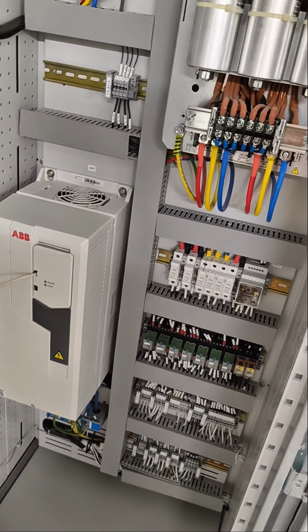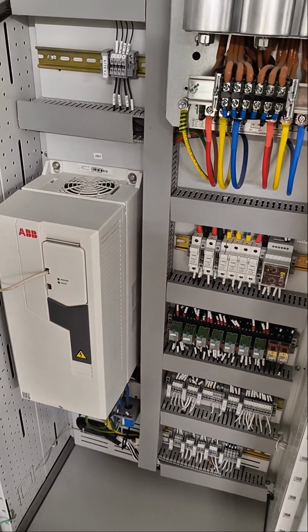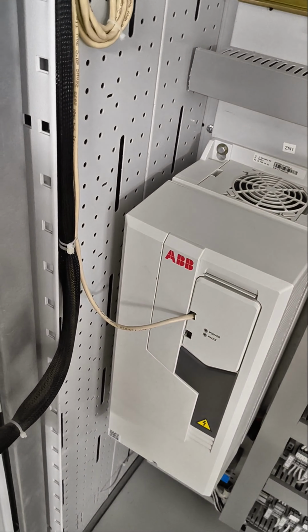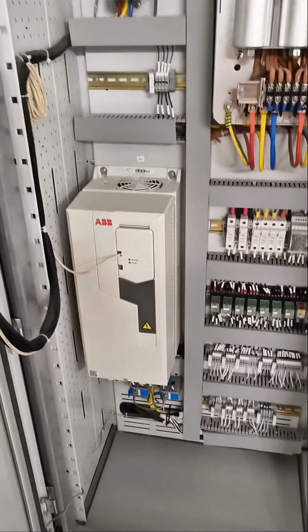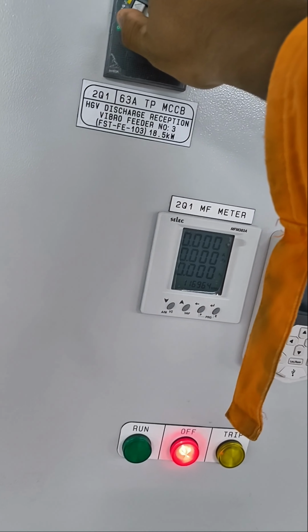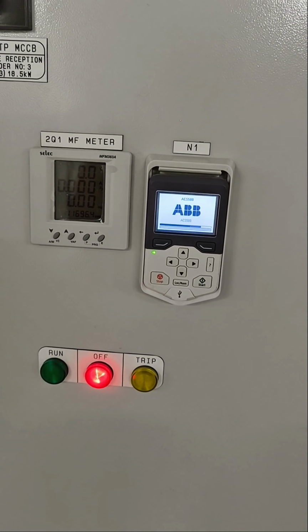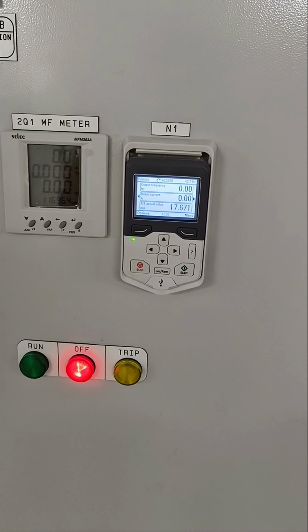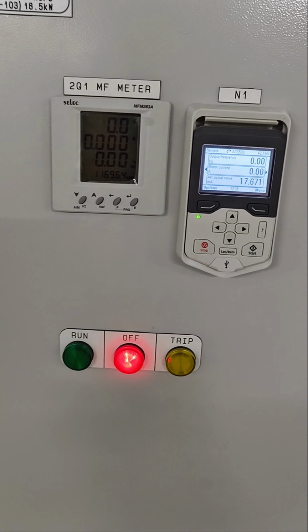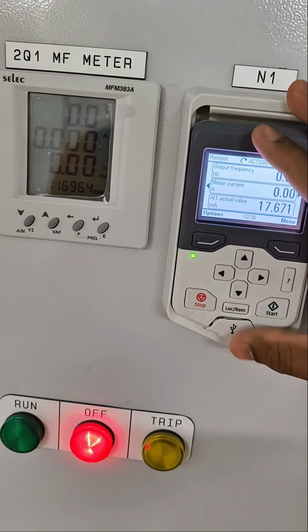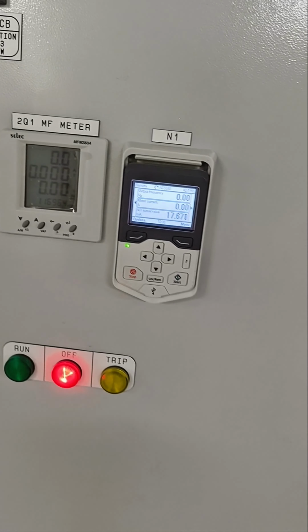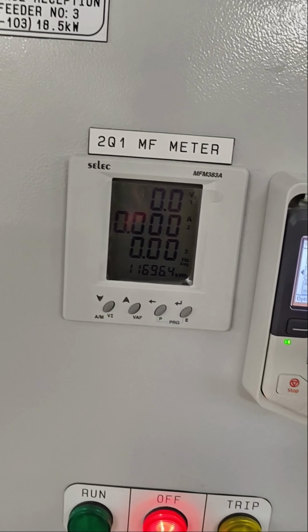Okay, so for that, now we are going to discuss how we can find the run hours in the ABB ACS 580 VFD. Let me close the door first. It's not closed properly. Now it's closed properly and locked. Now we are going to energize the VFD. Now the power supply is turned on and we will wait a while until the HMI is healthy. Now we can see our HMI is also healthy. This is called the HMI of the VFD, which is used to monitor or display the parameters inside the VFD.